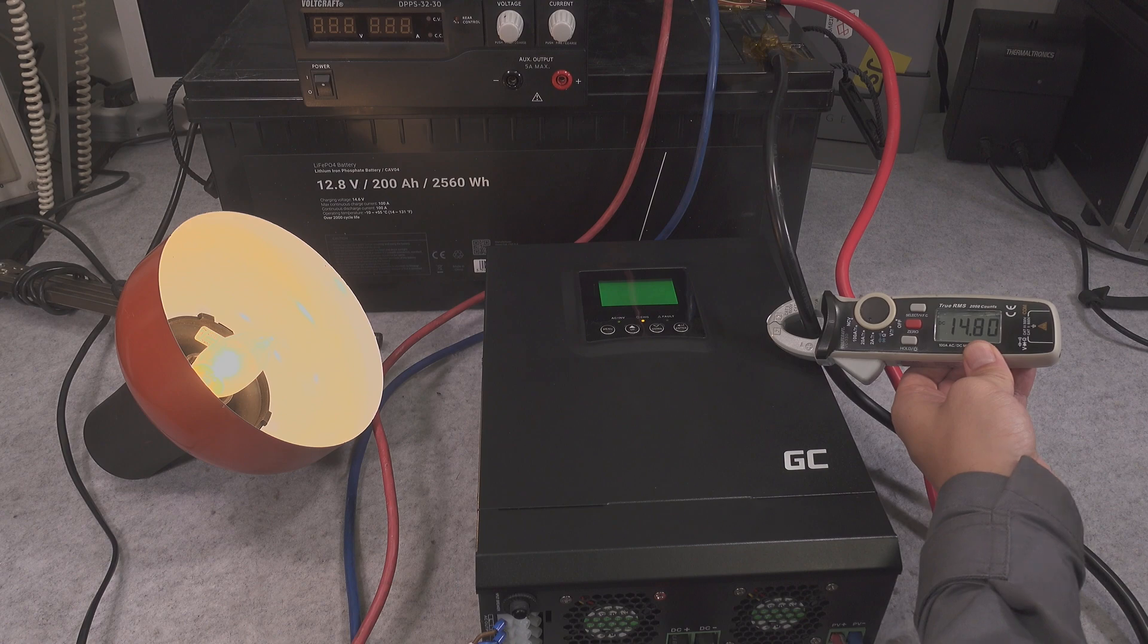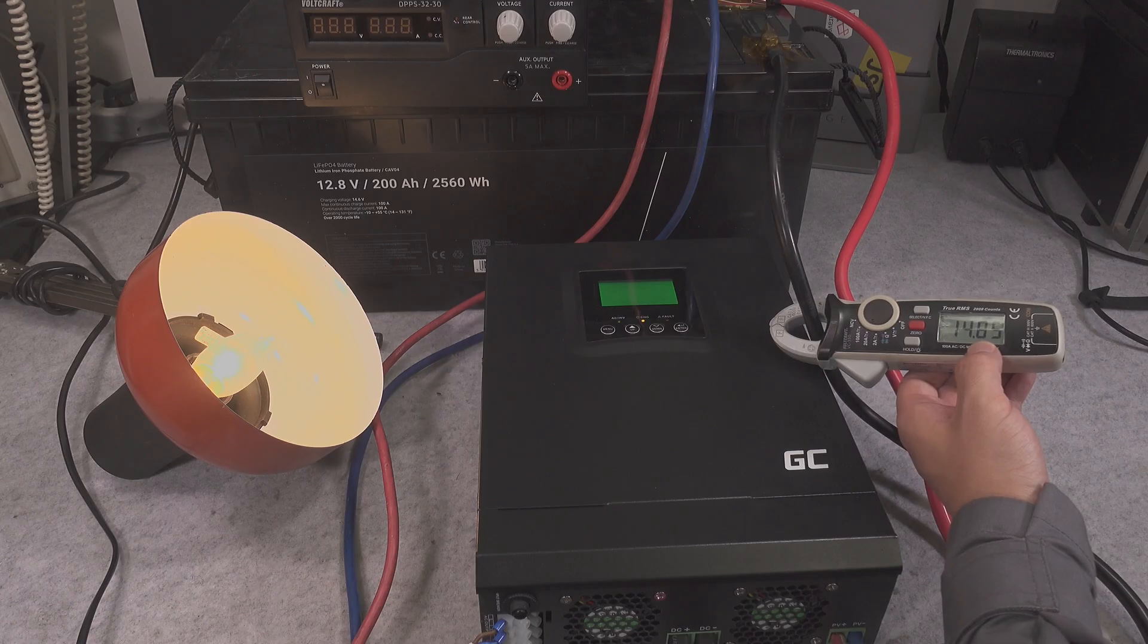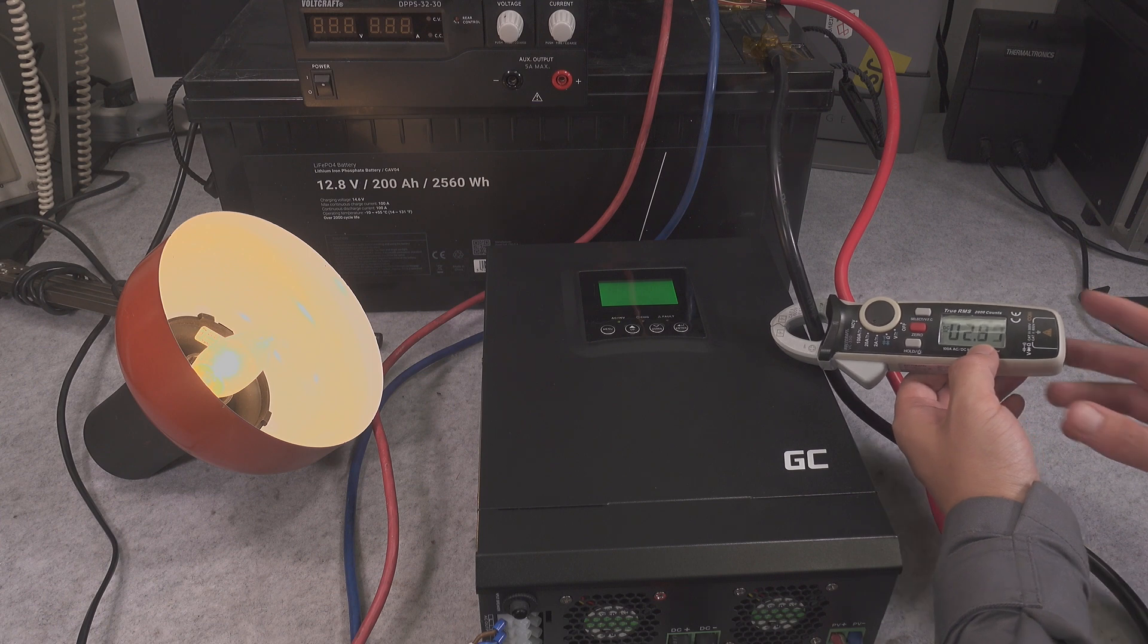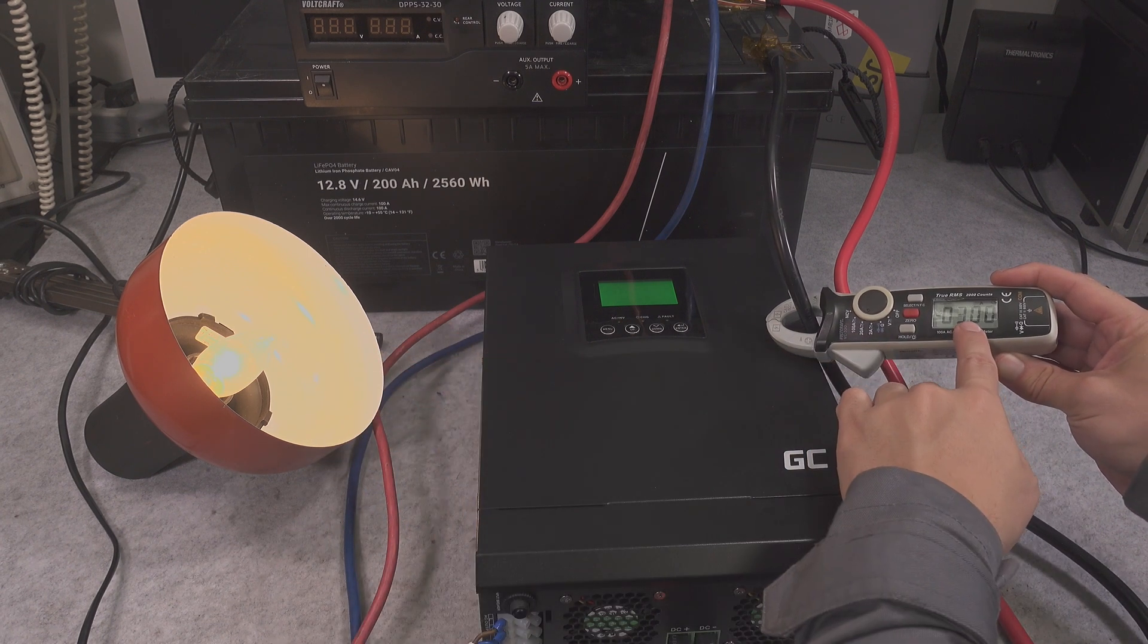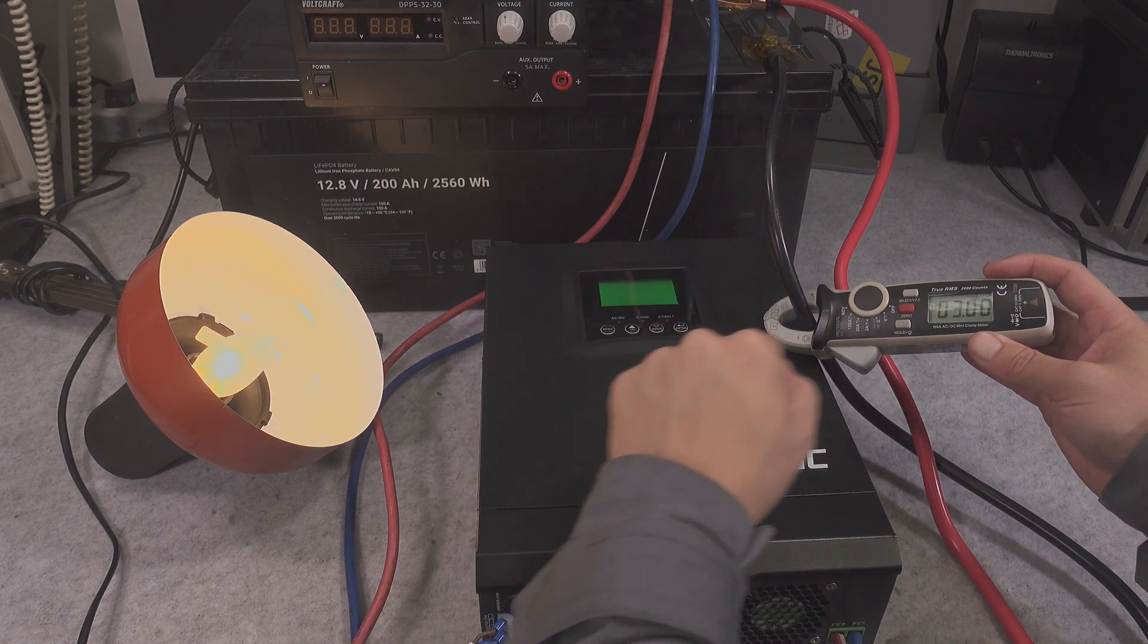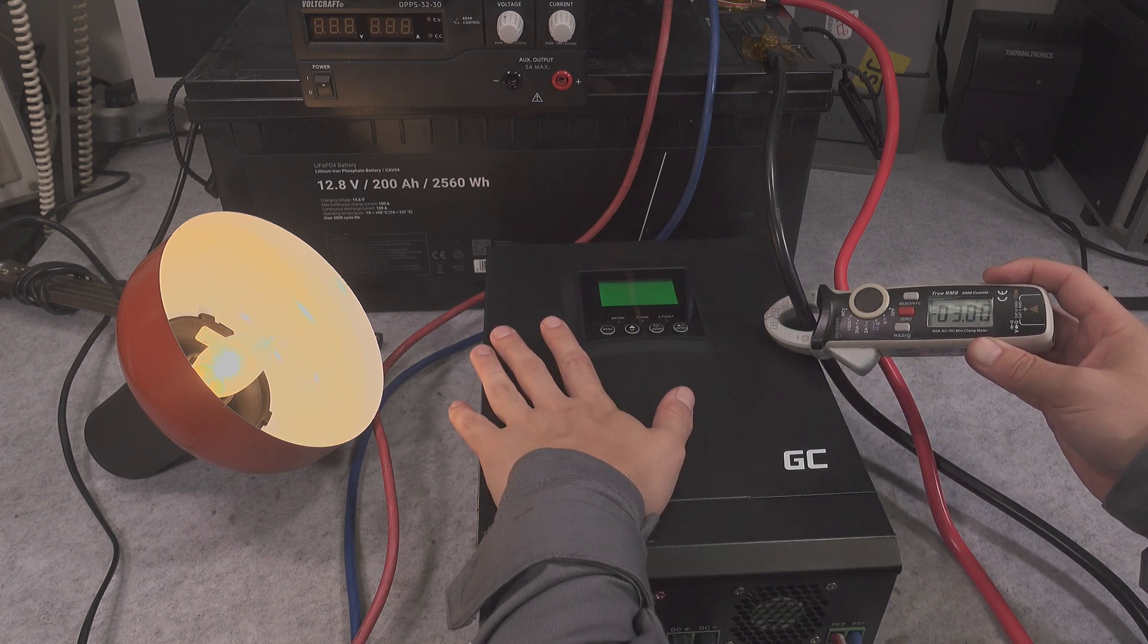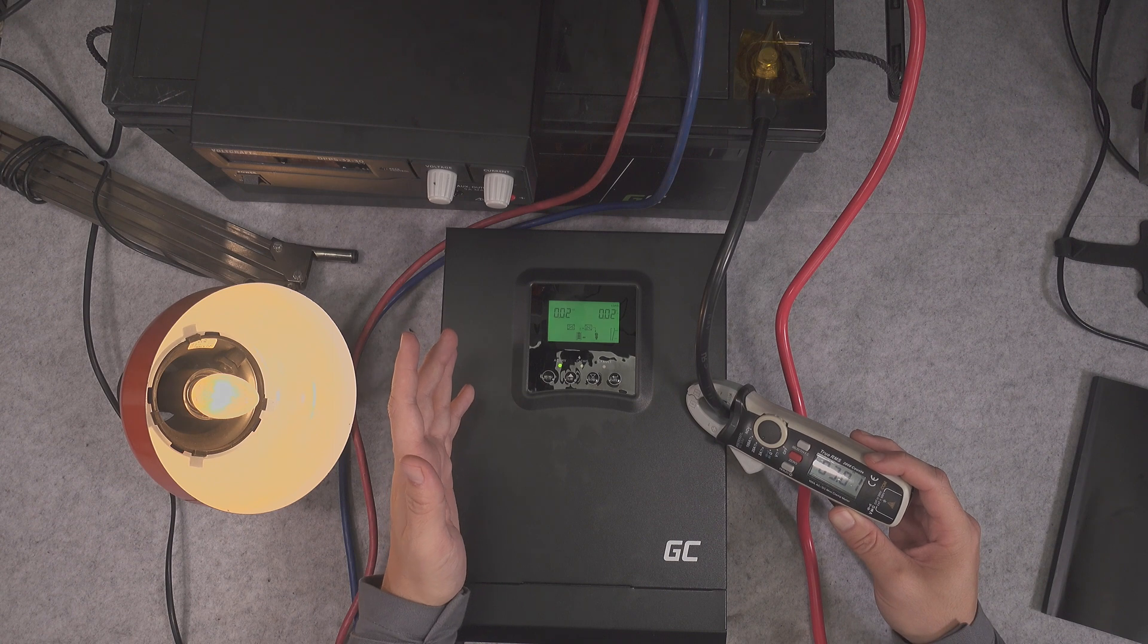Here we are going to be simulating power outage and I will disconnect our grid. There was a tiny blink and now the inverter is working. We are pulling power from battery. In my use case, in that condition where the battery is going to be low, we are going to be starting our gas generator.